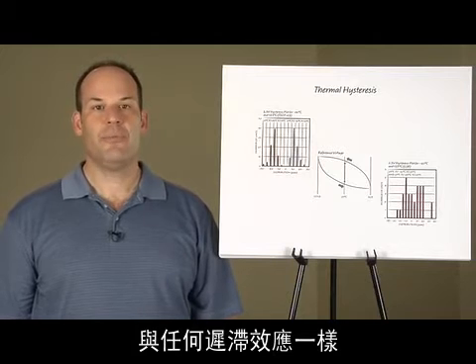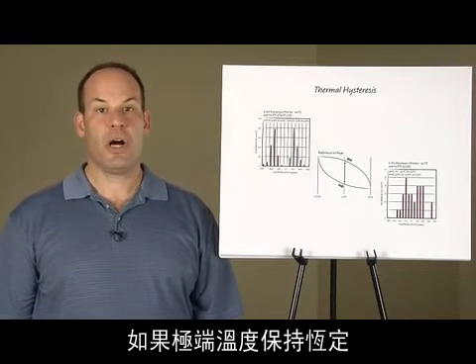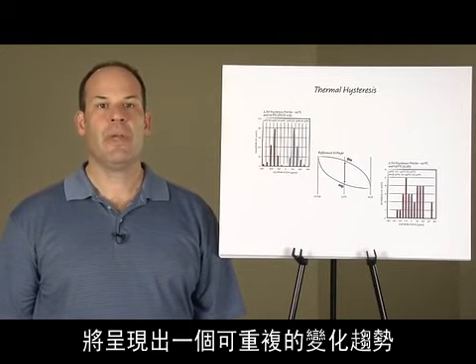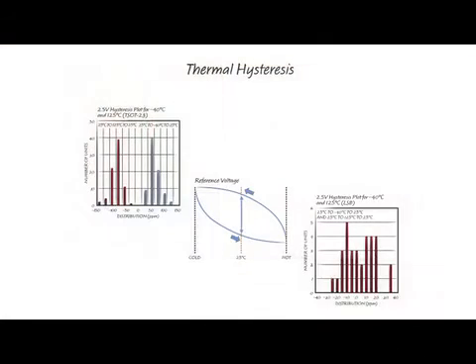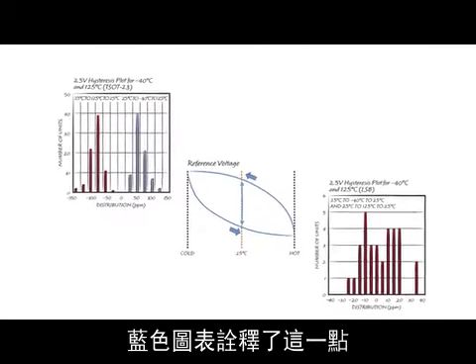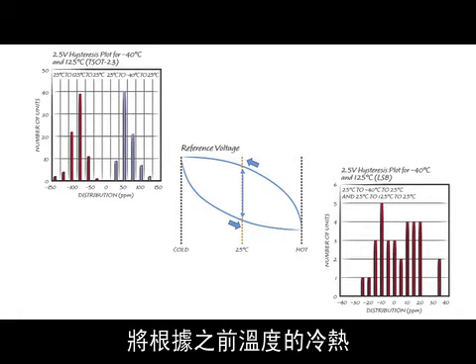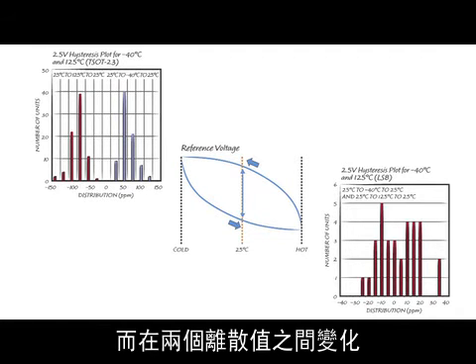As with any hysteretic effect, if the temperature extremes remain constant, the output voltage will follow a repeatable curve versus temperature as the temperature is cycled. This is illustrated by the blue diagram. Note that the output voltage as measured at room temperature will vary between two discrete values depending on whether the previous temperature was cold or hot.